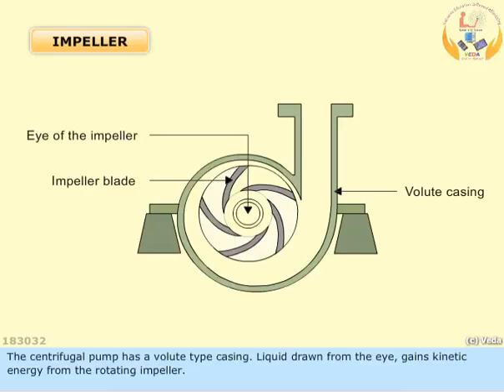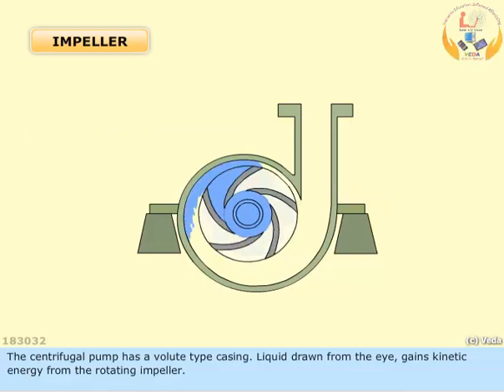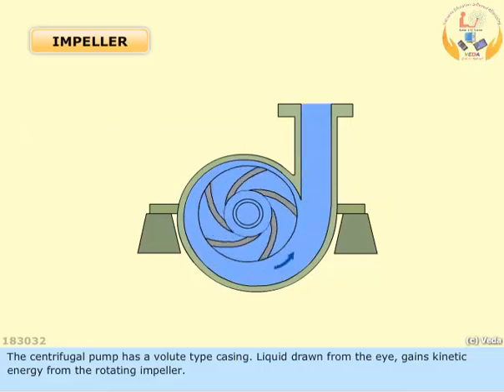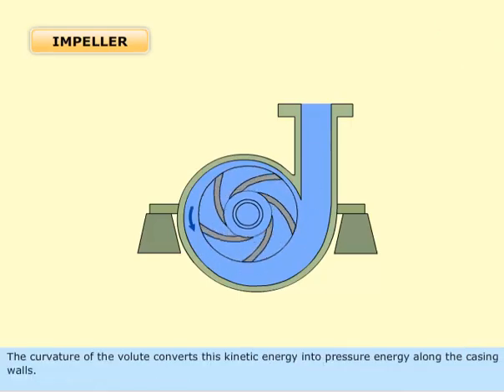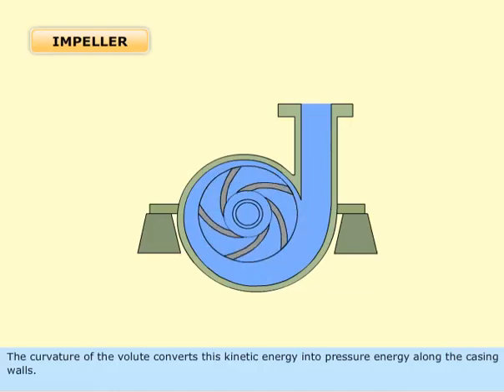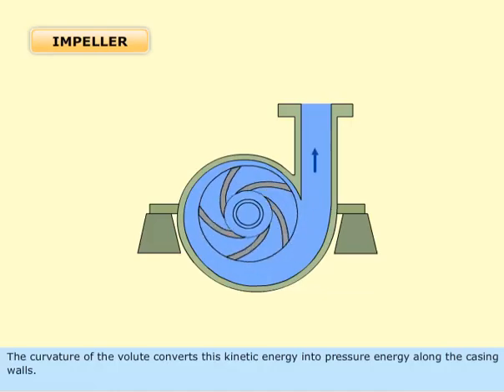The centrifugal pump has a volute type casing. Liquid drawn from the eye gains kinetic energy from the rotating impeller. The curvature of the volute converts this kinetic energy into pressure energy along the casing walls.